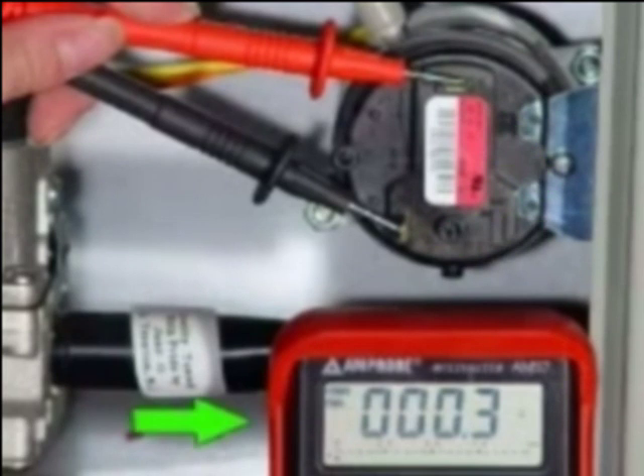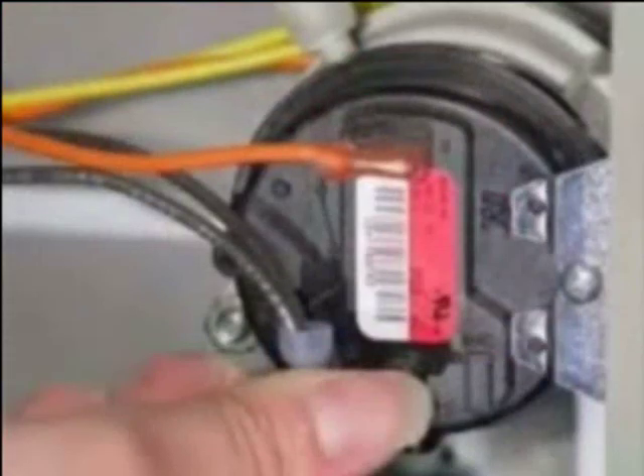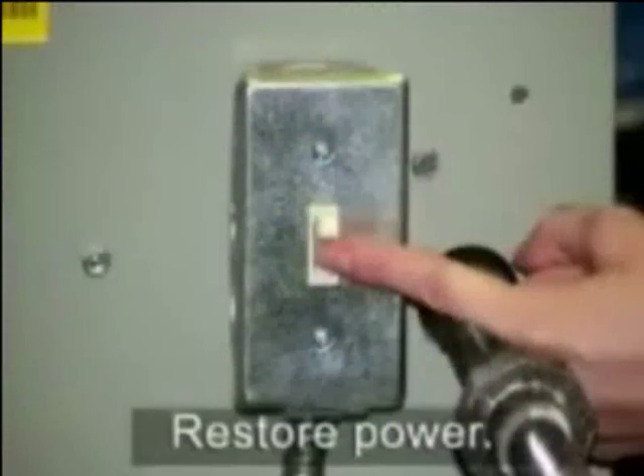A shorted vent pressure switch will measure zero resistance. Replace the switch if it is shorted. An open vent pressure switch will measure infinite resistance, indicating the switch is not shorted. When you have finished testing the switch for a short, replace the wires and remember to restore power to the furnace.